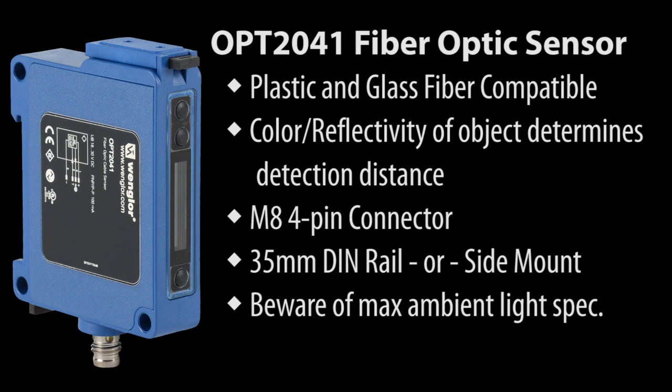Beware there is a max ambient light spec. Bright sunlight can be greater than the 10,000 lumen max spec, so you'll want to avoid using these in direct sunlight.